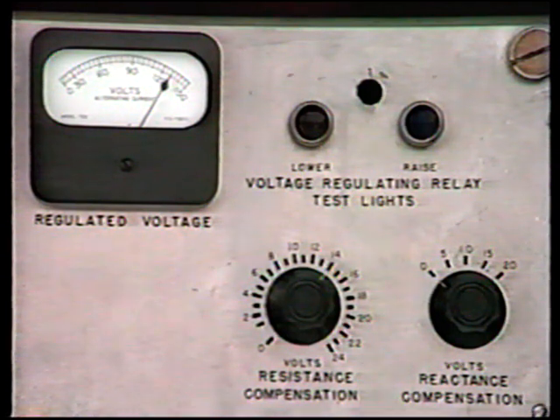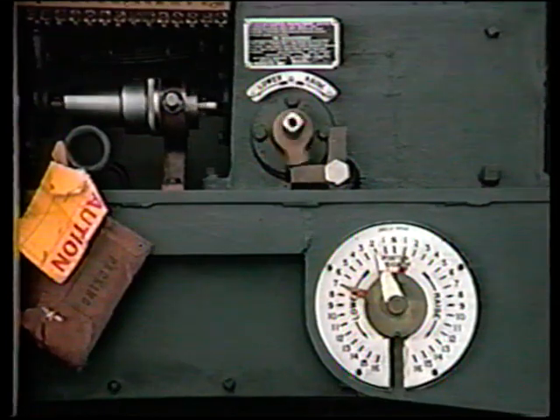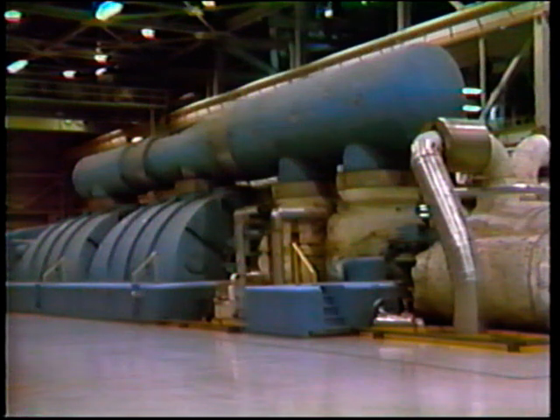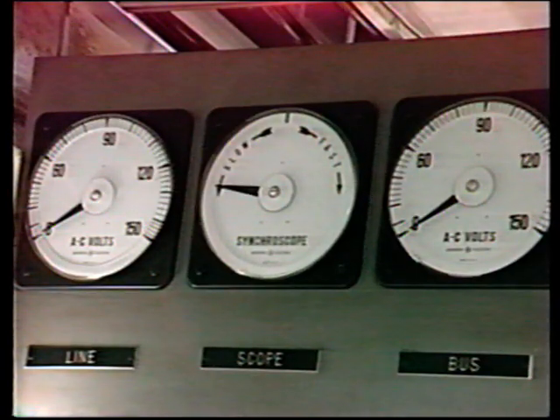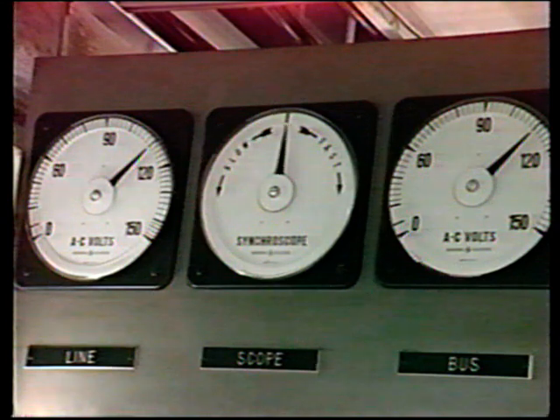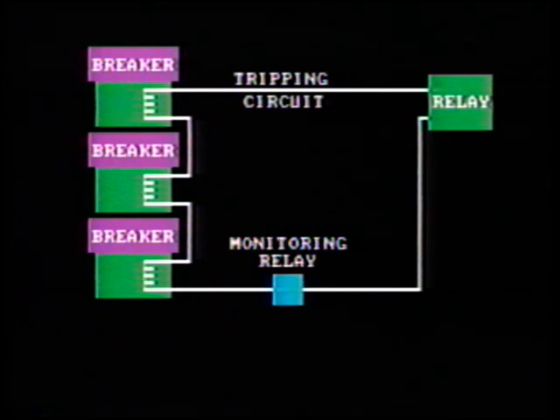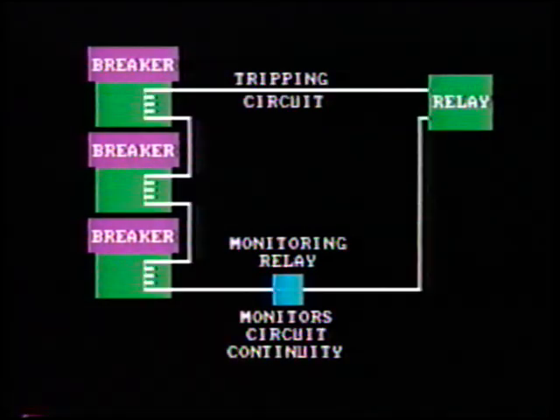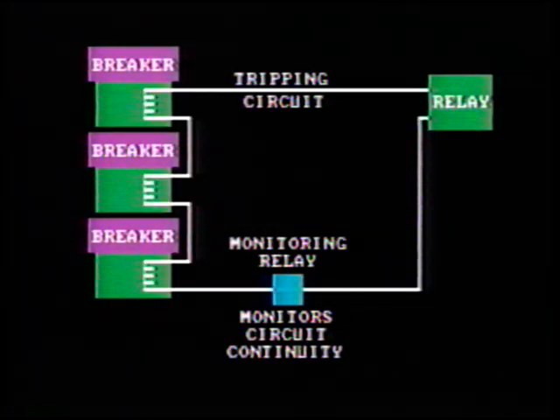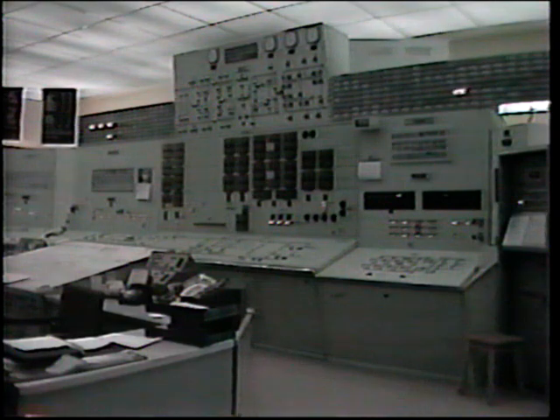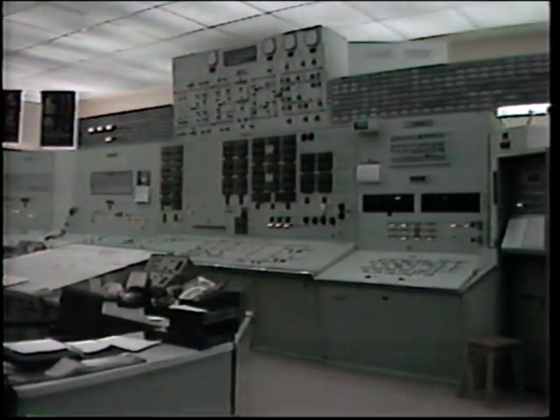One such classification is that of regulating relay. A typical example is the type of relay used to change the taps on a transformer. Another regulating relay is that used to adjust the governor set point on generating equipment and so control the power output. Synchronizing relays are used to check the phase angle before allowing the paralleling of two systems or an incoming generator. Another type of relay is the monitoring relay. An example of this is where the relay is used to monitor the continuity of circuits within breaker trip circuits. Any failure will result in an alarm to the operator.